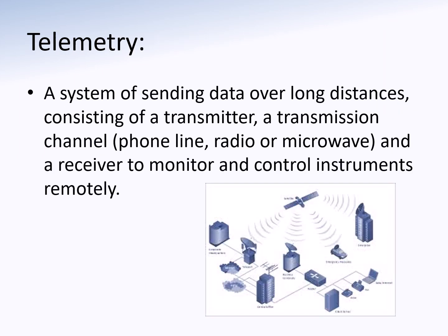Telemetry. This is how that signal is being sent from your remote site to a central location, right? So it is defined as a system that's sending data over long distances, consisting of a transmitter, transmission channel, and a receiver to monitor and control instruments remotely. Right. So, like we said, when you're talking about SCADA, it's the supervisory control and data acquisition, meaning that you can both monitor and control the pumps, or you can manipulate the system remotely.